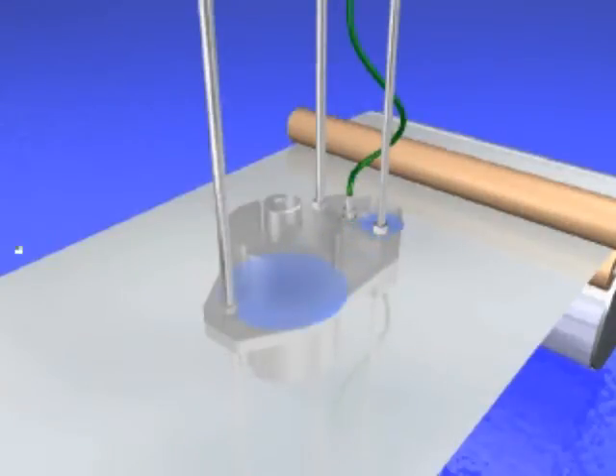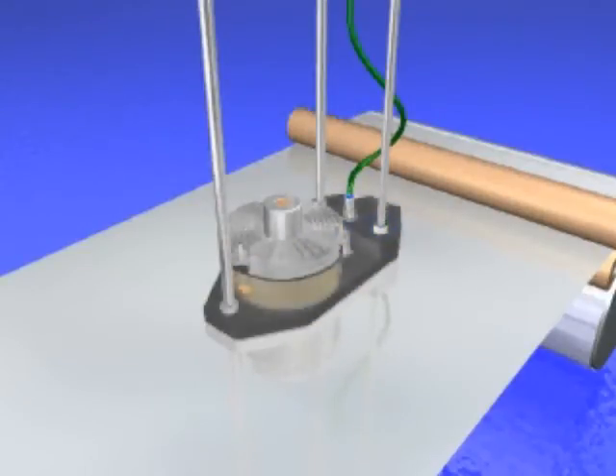The partly magnetized material segment approaches both receiving coils of the IMPOC measuring system at the existing strip speed. The intensity of the magnetization decreases the farther the strip segment is away from the generator coils.